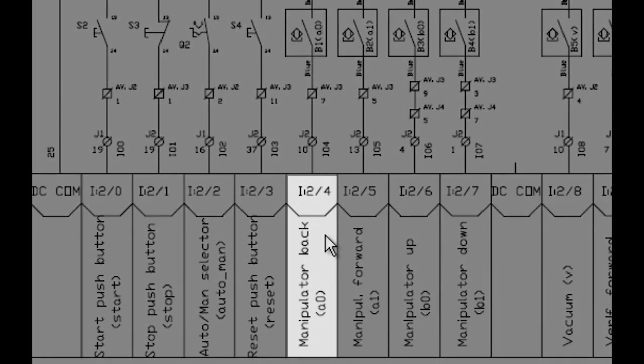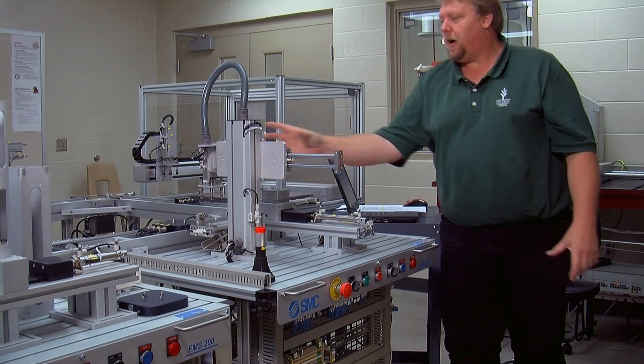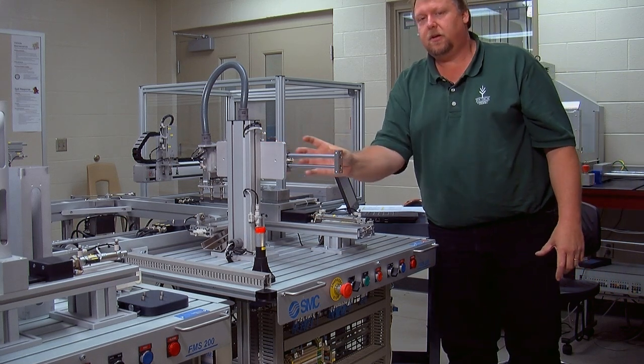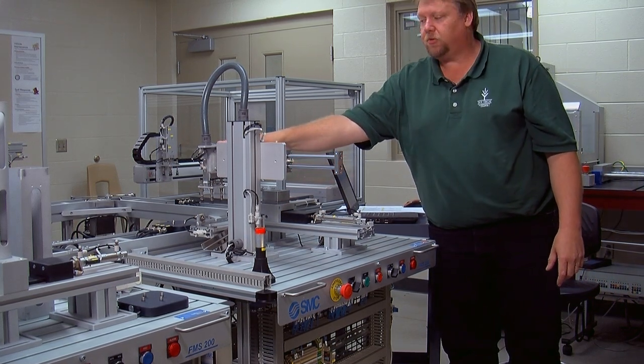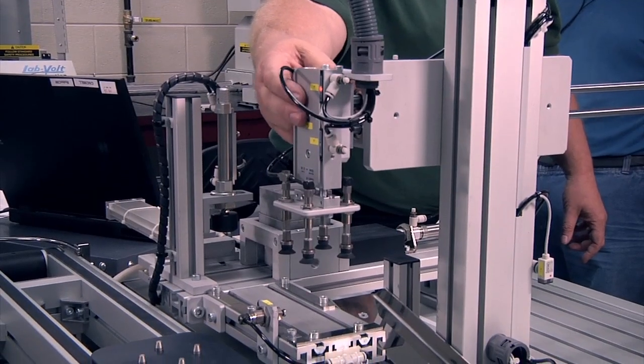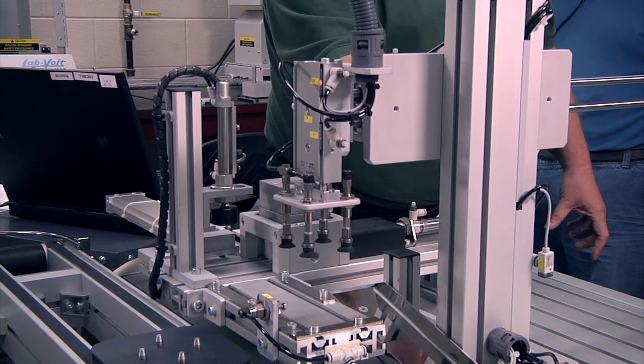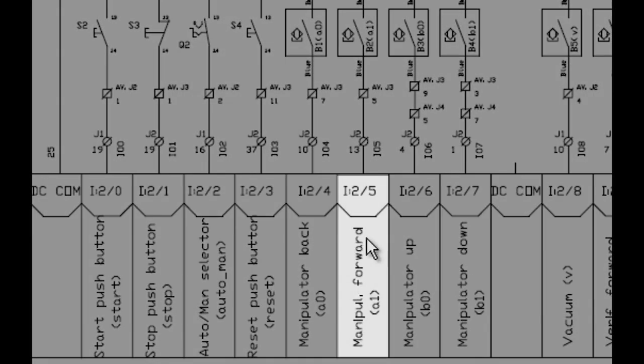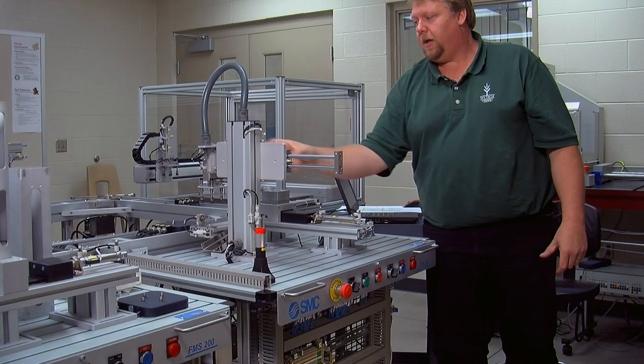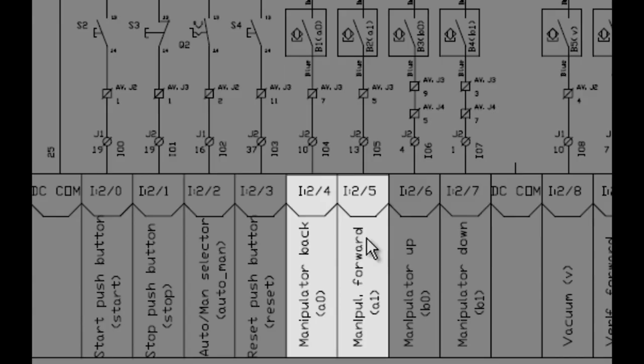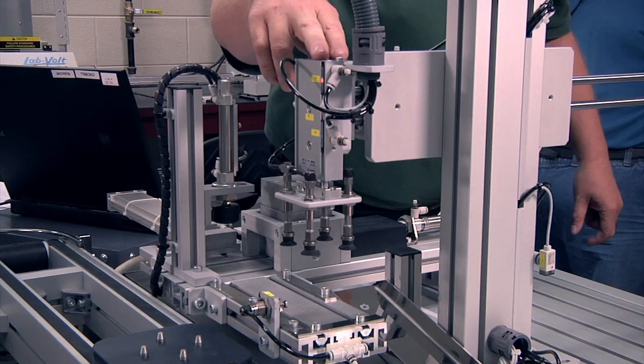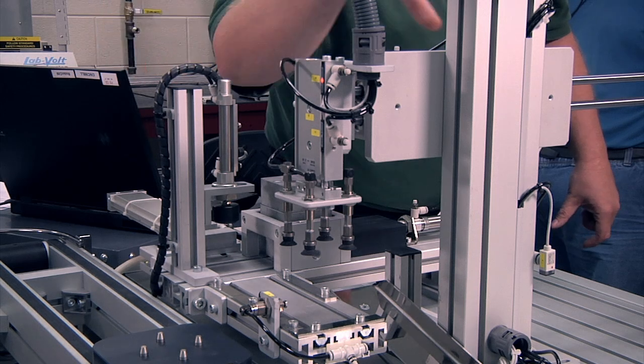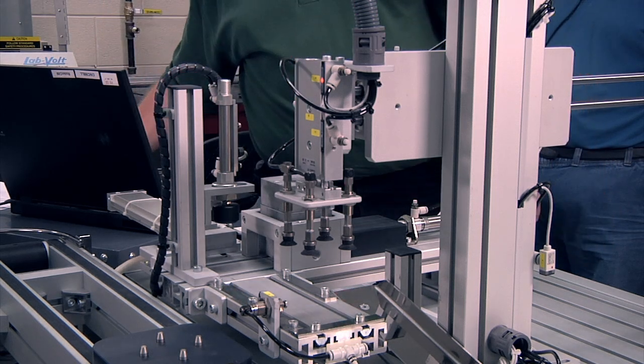Our next one is manipulator back, referring to this actuator right here. When it is in its normal state, it is back — you can see the actuator attached here is in the back position. Manipulator forward is the next input, labeled I:2/5. Manipulator back and manipulator forward are I:2/4 and I:2/5. So when this cylinder energizes, it's going to take this out here back and forth — that's why they labeled them accordingly.